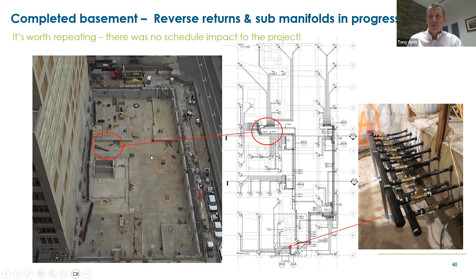The next phase of works is to connect up these sub-manifolds and run them back in what we call reverse return. The important thing with reverse return is that the distance from this main manifold to the tip of every single pile is always the same dimension, so you get an equal, balanced system.